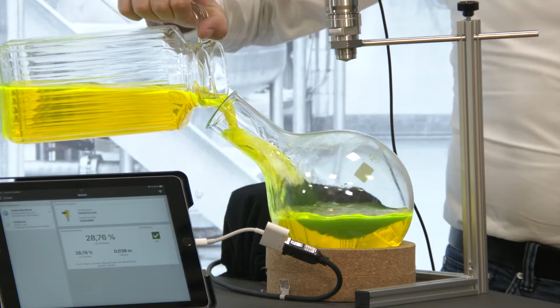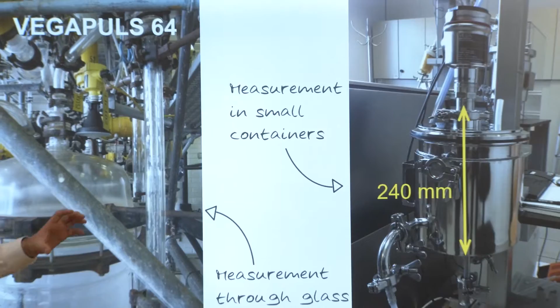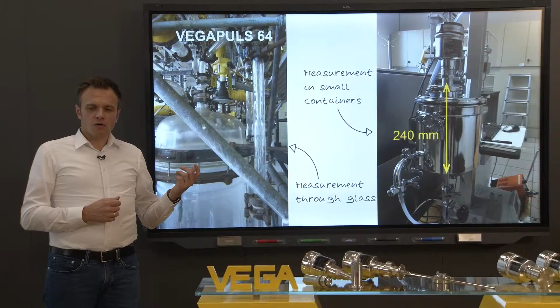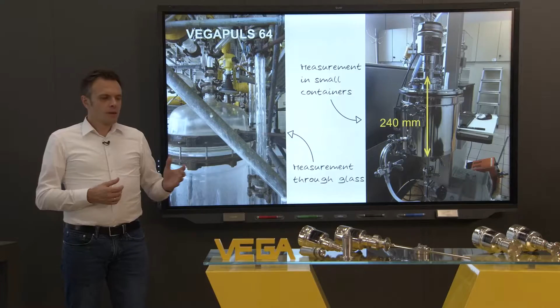When we now have a look on a real application from a VEGAPULS 64 with a reactor made out of glass, because internally we have a high demand on aseptic, and we have a really high chemical aggressive media inside. This is very easy measured with a VEGAPULS 64 and with plastic horn antenna, so it's a standard easy sensor. We measure it through the glass of the water column, and we have an easy measurement from a standard device with a high demand application.